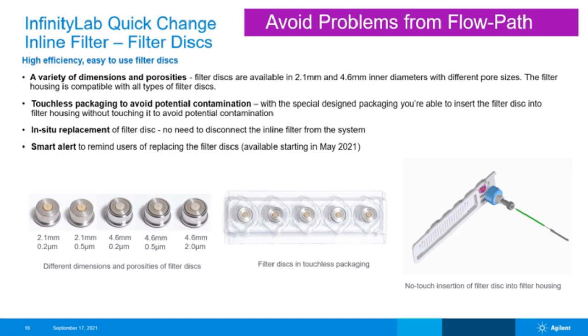Starting from approximately May 21, there will also be a new feature in Smart Alert for the inline filter to remind users of replacing filter disc based on time interval or number of injections. If users have some experience on how often they need to replace a filter disc and would like to do the replacement before clogging happens, then they can activate the Smart Alert feature.